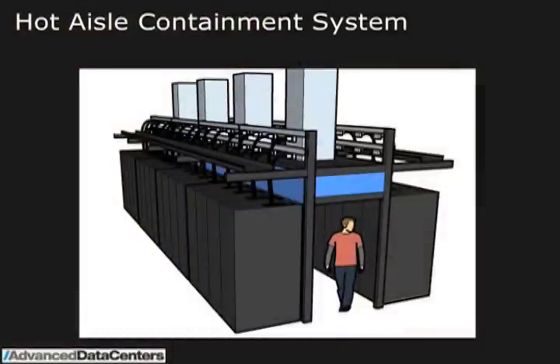If there is no mixing or recirculation, supply air and rack intake temperatures will be essentially the same. If there is some recirculation, they would differ. The goal is no mixing — the hot aisle will be physically enclosed, so when working properly there will be no mixing, though there will always be a little bit of leakage. Regarding whether the landlord is supplying the ducted returns as part of their package — yes, and the next presentation from Wright Line will explain that in more detail.